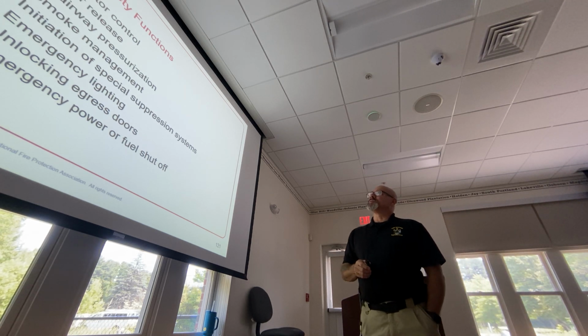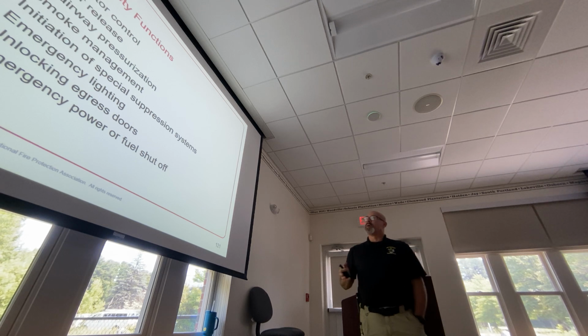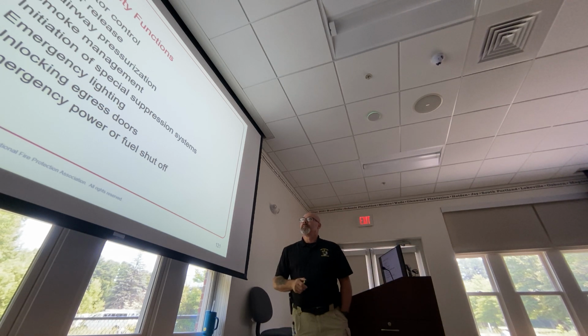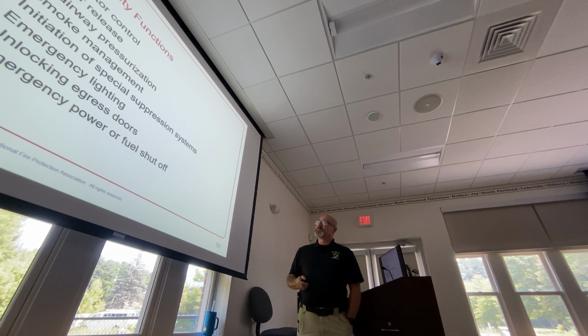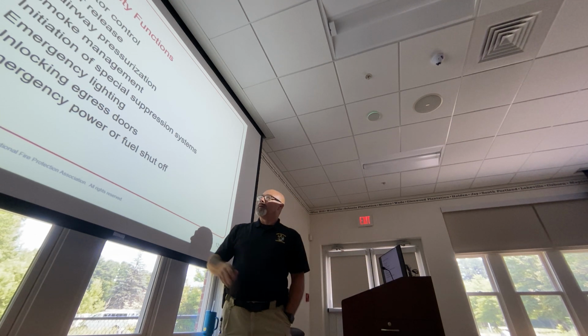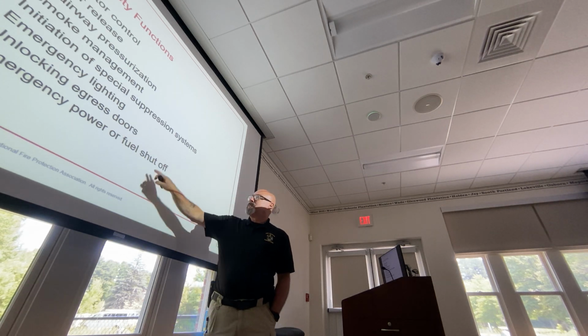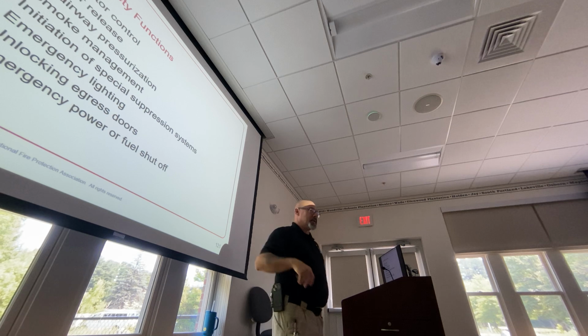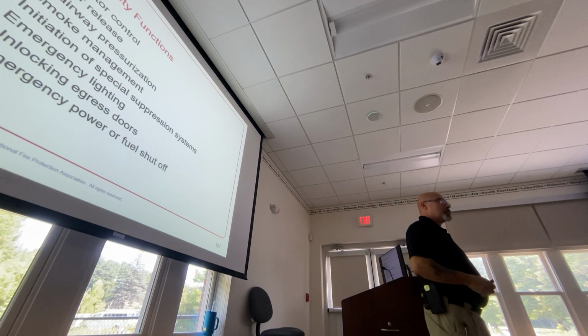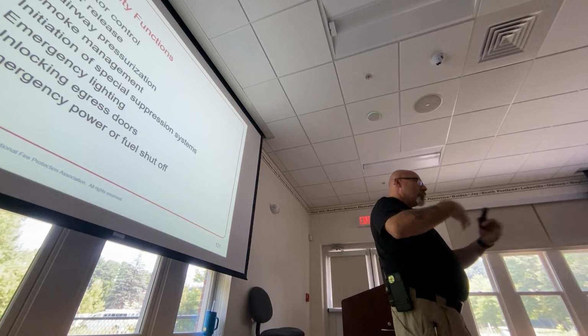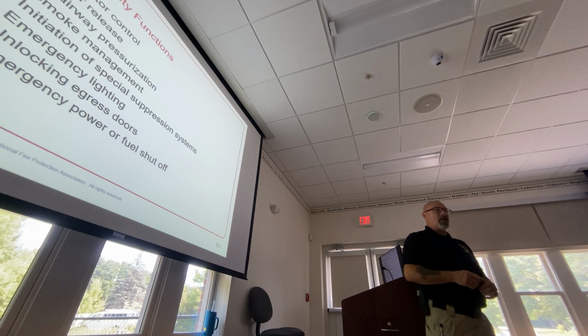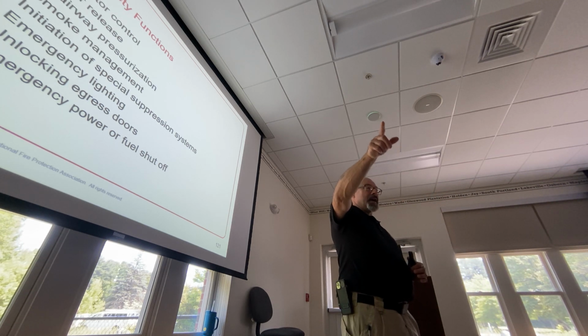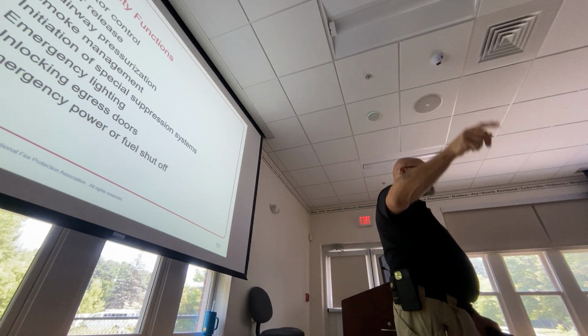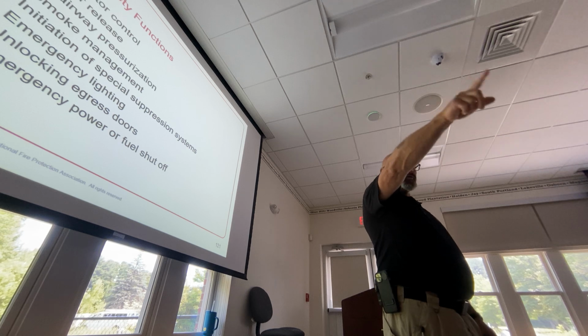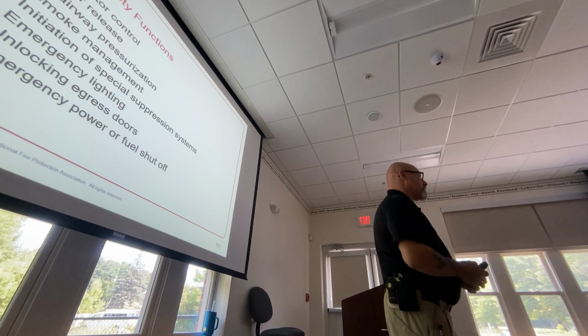All right, fire safety functions: elevator control, door releases, stairway pressurization, smoke management, initiation of special suppression systems, emergency lighting, unlocking of egress doors, emergency power or fuel shutoffs. All of those things can be connected or should be connected to the fire alarm system. I may have a door that is held open with magnetic door holdopens. Those doors may shut when the fire alarm goes off. Maybe I can't go through those doors on a regular basis. The fire alarm activates, those doors unlock, and I can go through those doors now. Okay?